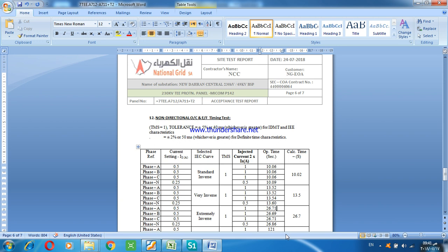Because this relay doesn't see another. But sir, if there are two CTs, suppose bus breaker and middle breaker, they should not do summation before entering the relay. I think they are making summation before the test plug and then go to the relay with only one CT. Here it is looking like low impedance, like all CTs are going parallel. But in general practice, they make summation and then send only one CT to the relay. Yeah, actually, if they make it direct, then there is no problem. If the summation is in the relay, then we have to take care. Yes, you have to take care.